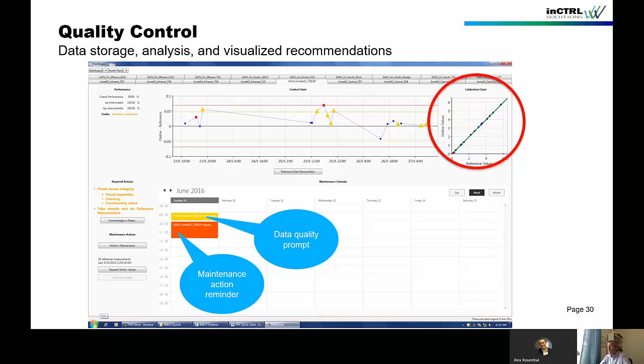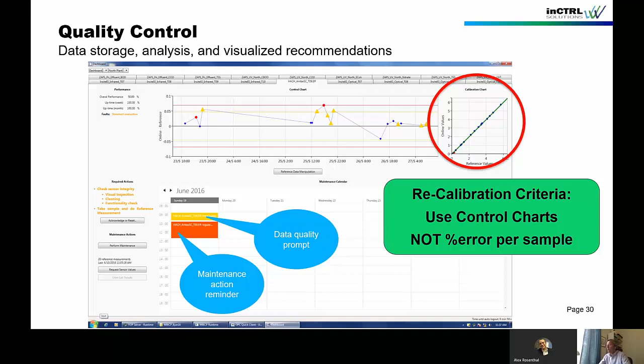If you set up your recalibration criteria, use control charts, right? So the control charts are set up so that you detect systematic errors. Don't do percent error per individual sample. That just gets you into trouble because you follow the random noise. Okay, so this is the reference measurement. So let's say you do that once a week. So that's a typical recommendation.